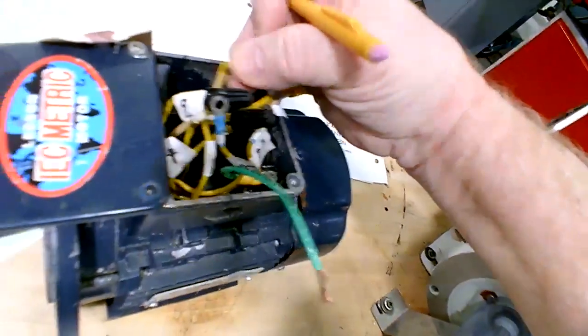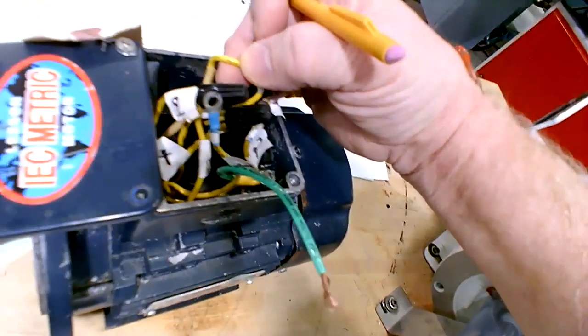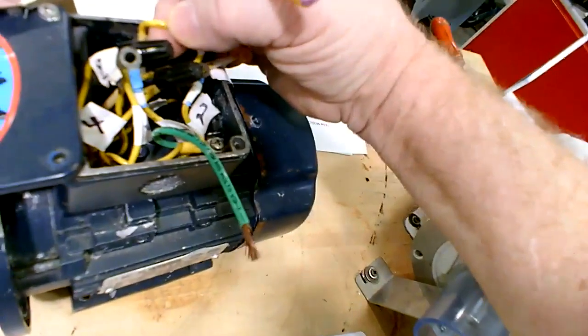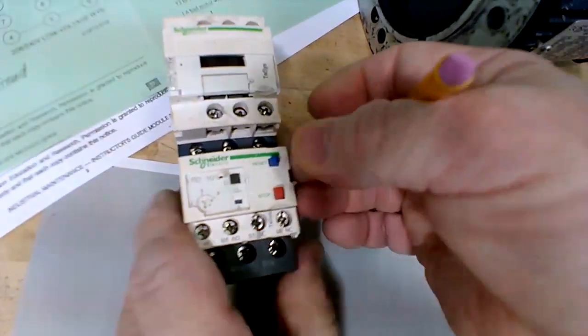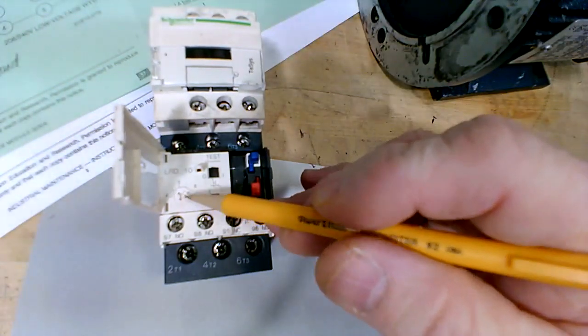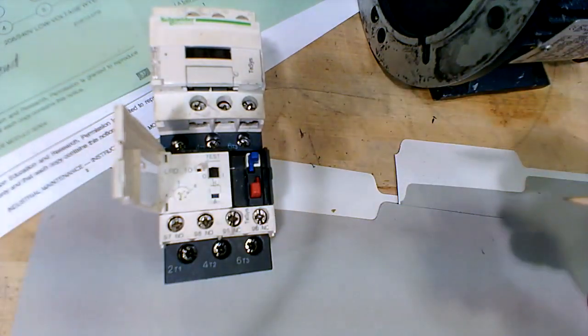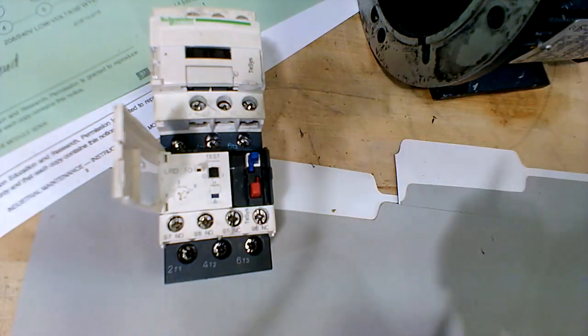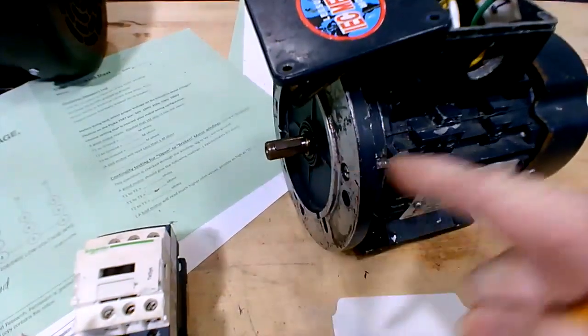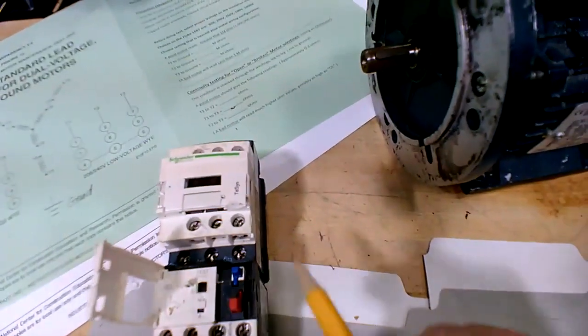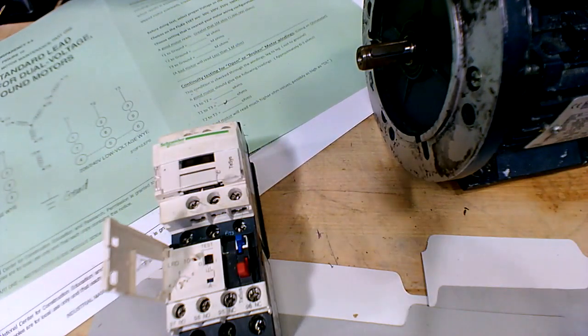Like we have here, we got a ground wire here. These windings are supposed to be isolated from ground because of the insulation around them. So what happens is when the insulation gets hot and cracks, or if it ages and dry rots, or gets hot, cracks, or melts for various reasons. Like if the bearings lock up and the motor gets in a bind, and maybe somebody didn't set the overload correctly on the motor starter. There's an overload on here. There's a dial, and that dial can be adjusted for so many amps. Maybe somebody has cranked it up way too high, which happens. They crank it up way too high above the proper rating, and then the bearings lock up, and it overheats the windings because the starter didn't trip out in time. And so you melt the wires, you have a meltdown. Okay, so that is just a domino effect that can happen.